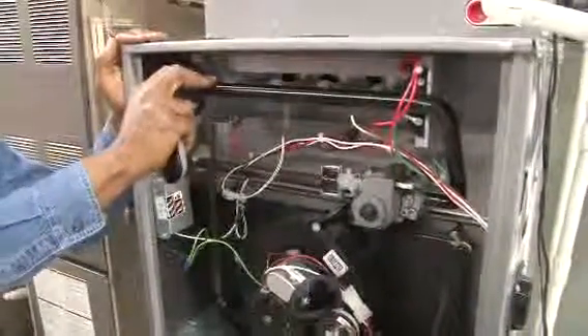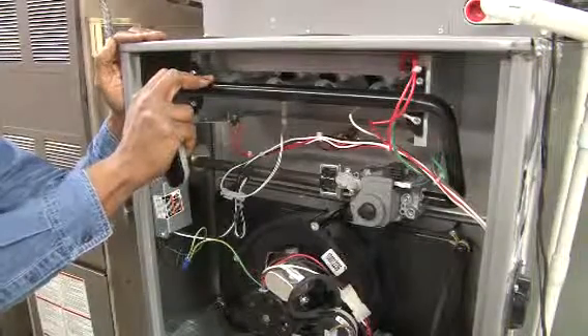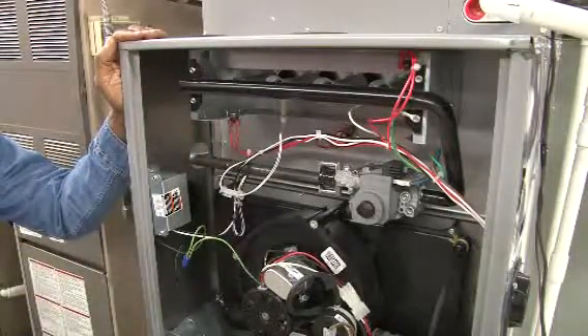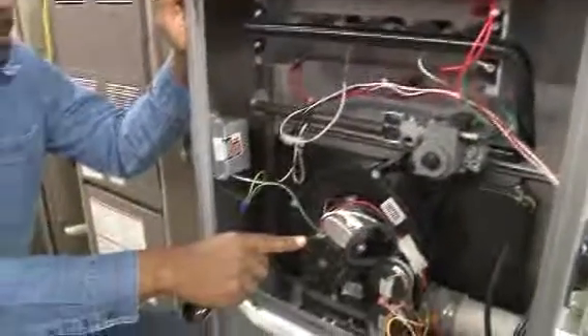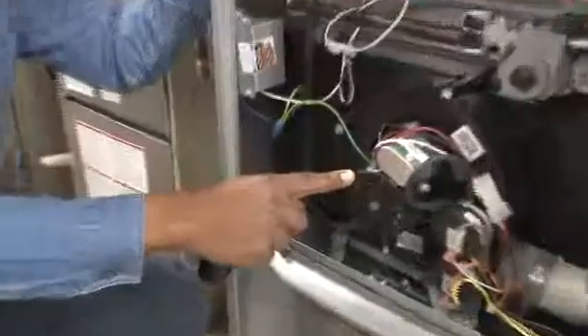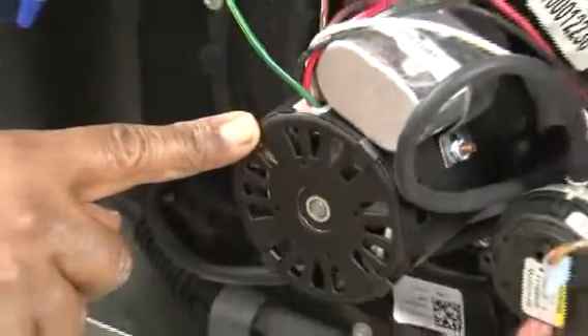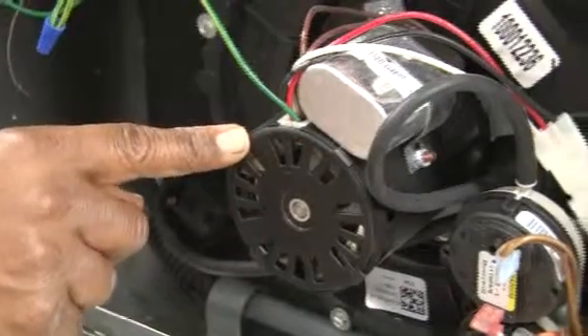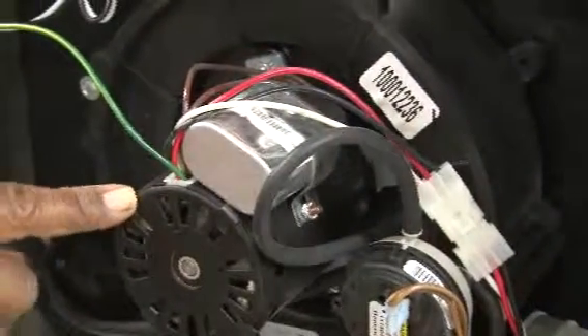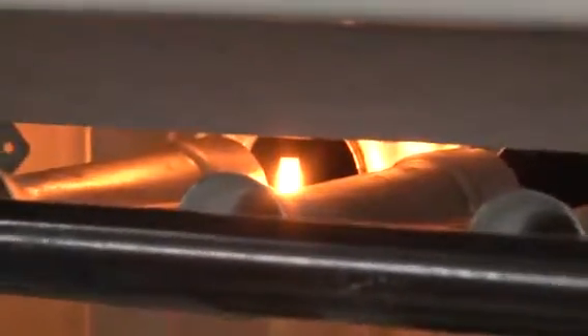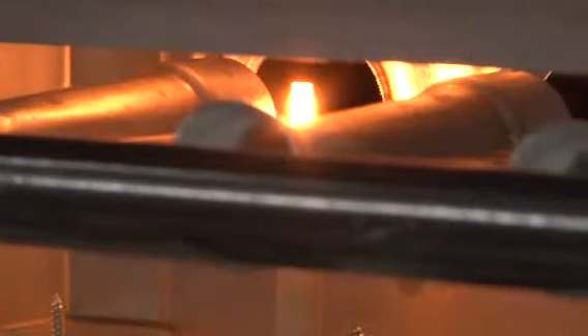Now, the next thing we're going to do is start up the system and talk about the sequence of operation. As the furnace starts up, the very first thing to become energized is the draft motor, which starts the blower, which is doing that now, and it goes through a pre-purge. The next thing it will do is start the ignition system. There is an igniter connected to the system, which will start to glow and heat up, to generate the heat to light the combustion gases for the burners.